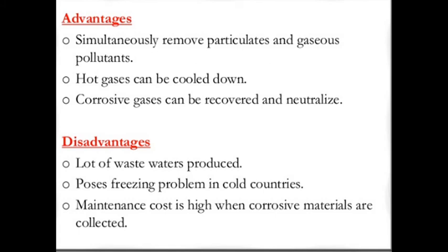Advantages and limitations of spray tower. Advantages: simultaneously removes particulate and gaseous pollutants. Hot gases can be cooled down. Corrosive gases can be recovered and neutralized. Limitations: a lot of wastewater is produced. Poses a freezing problem in cold countries. Maintenance cost is high when corrosive materials are collected.